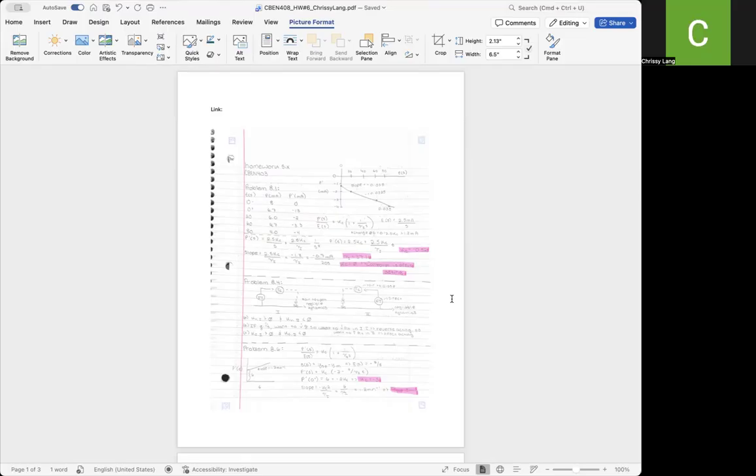After determining the process gain signs, you would consider how the controller output should respond when measured flow deviates from the set point. If the flow increases above the set point, we want the controller to move the valve in the direction that reduces the flow. Based on that, the controller in section 1 should be reverse acting, while the controller in section 2 should be direct acting. This ensures that the control loop always acts to move the system back to the set point.